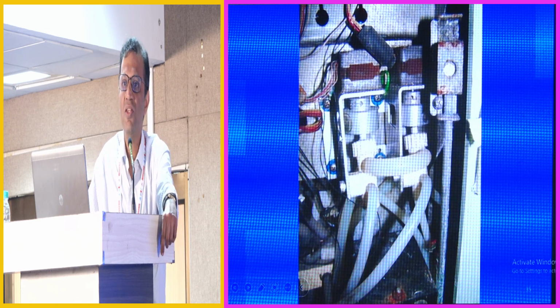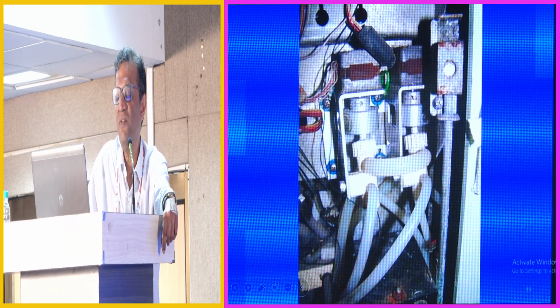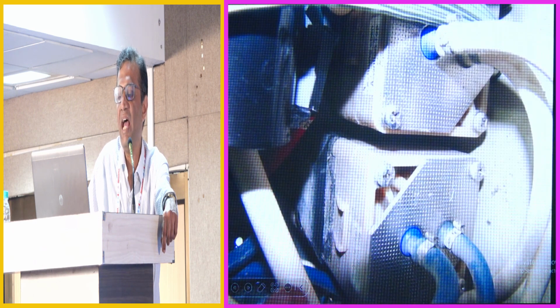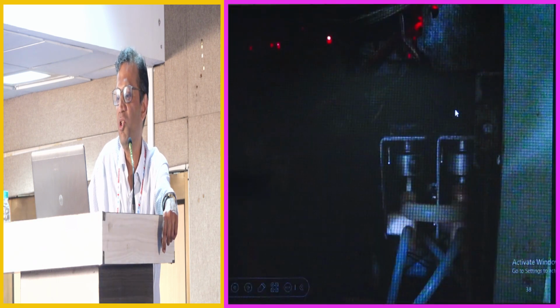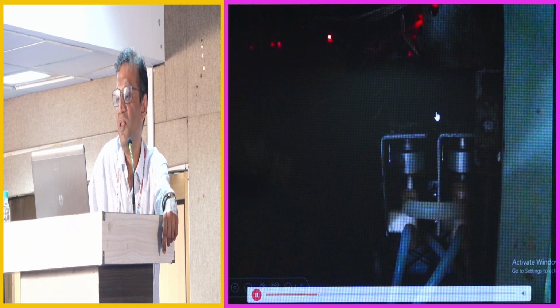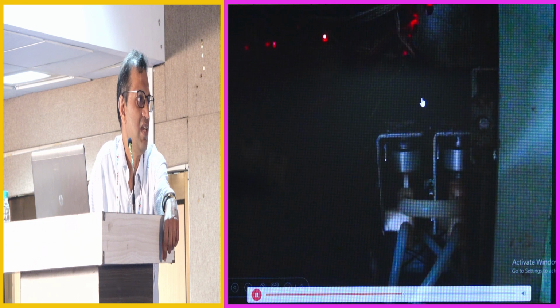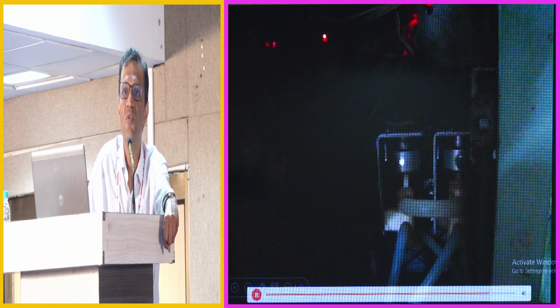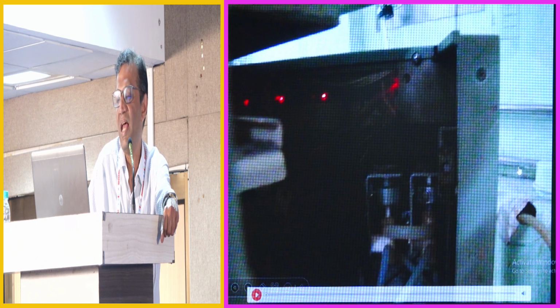Right. So the concentrate may be picked up in various different ways: by piston cylinder pumps in the Althin machines, by diaphragm pumps in the Fresenius system, and by peristaltic roller pumps in the B. Braun machine. Now, if you can see here, the pump on the left hand side is rotating about twice as fast as the one on the right. So the one on the left is the bicarbonate pump. It has to deliver 1.8 times as much bicarbonate as the acid concentrate.